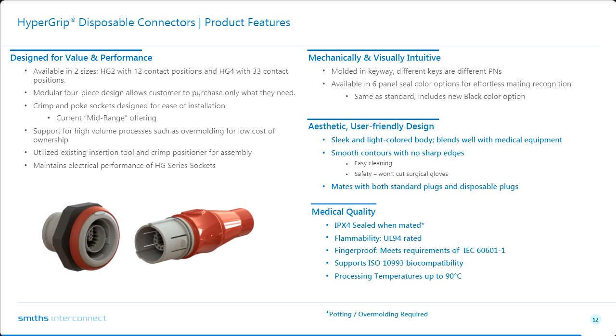The receptacle also meets UL 94, I believe HB. We meet fingerproof requirements for IEC 60601-1, and we meet ISO 10993 biocompatibility.